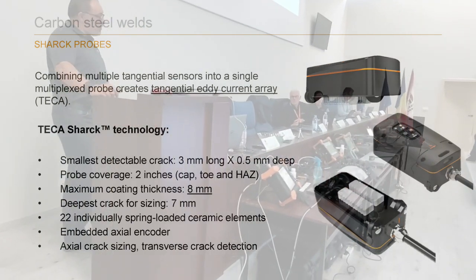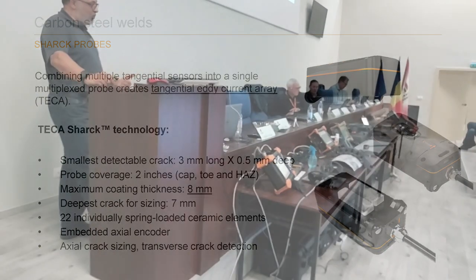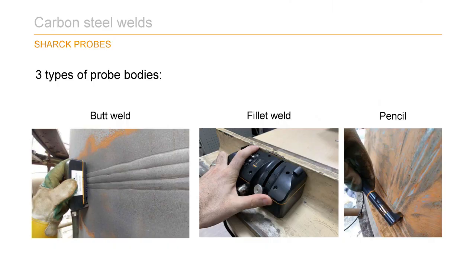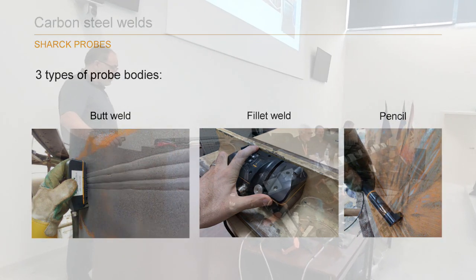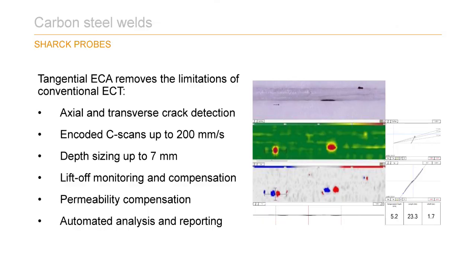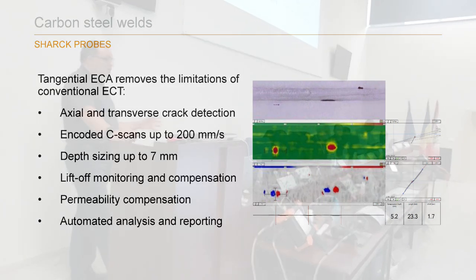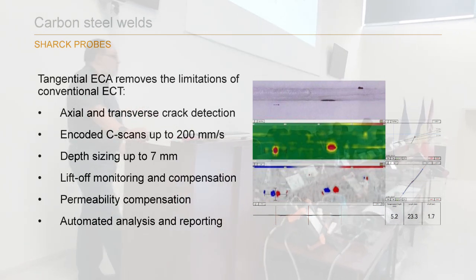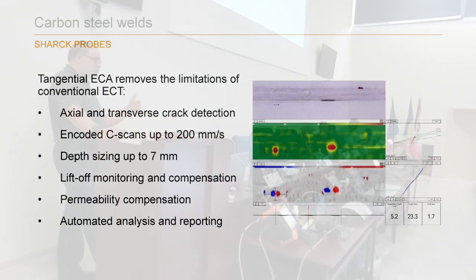Different types of probes are available, either for butt weld or fillet weld, or we also have a set of pencil probes. Those are the standard probes we call Sharck G2, so second generation. There's also a high resolution one, more dedicated to stress corrosion cracking detection and sizing, which I'll show later. With the standard Sharck probe, we can size depth up to 7 millimeters. If it's deeper than 7 millimeters, you'll be able to see it, but you won't be able to measure if it's 7.5 or 9. The limit is 7 millimeters.